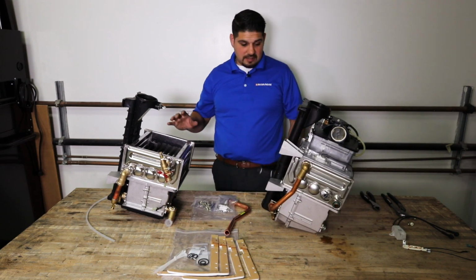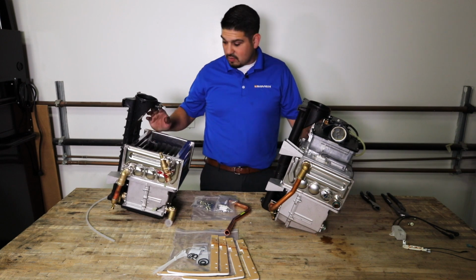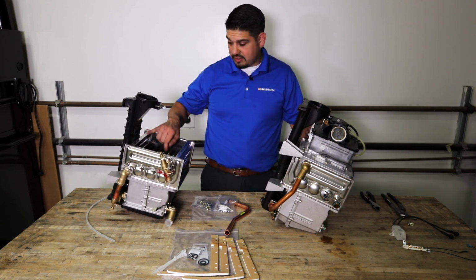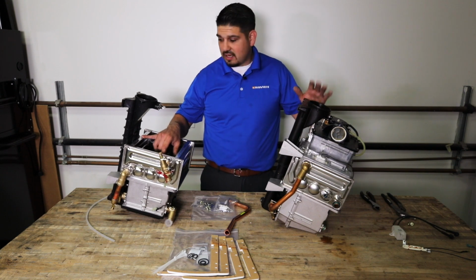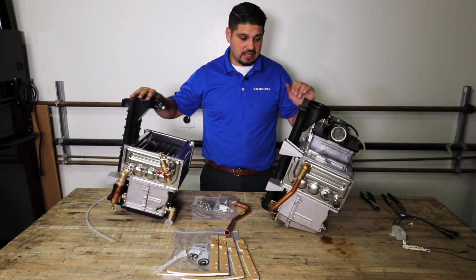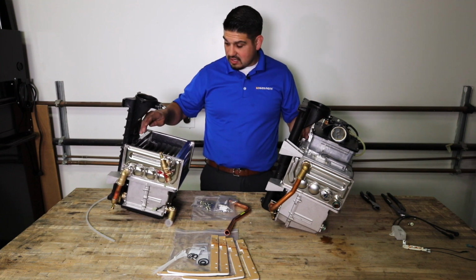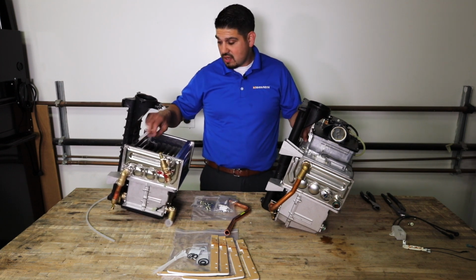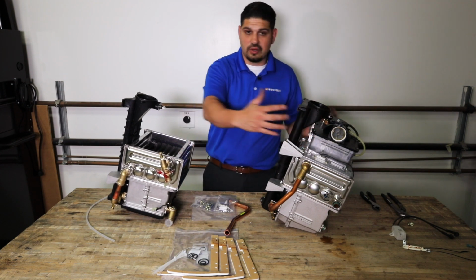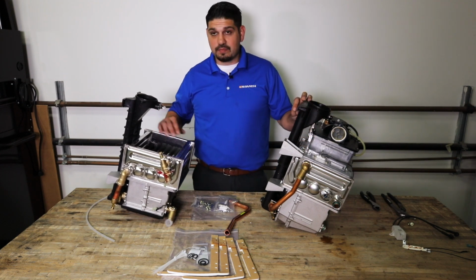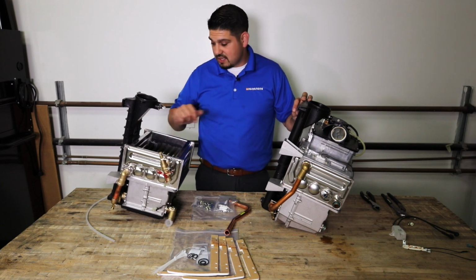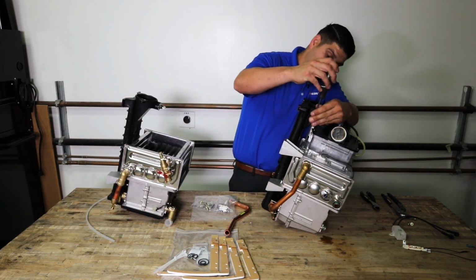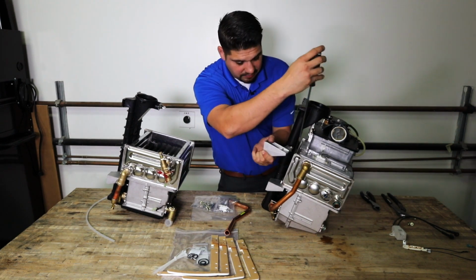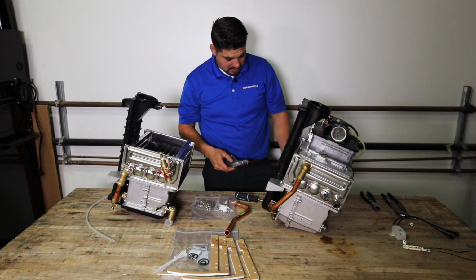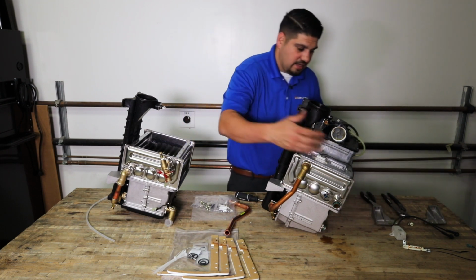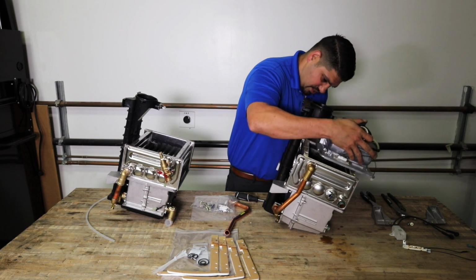With the new heat exchanger design on this one compared to this one, what they've done is there's a little hole in the middle that no longer exists. The angle of your exhaust ducts and getting a screw jammed, it was pretty hard. So what they did was they eliminated this center hole on your heat exchanger. So when you transition over your burner, you're not going to be able to put that hole in there because it doesn't exist anymore. So just go ahead and remember that. Keep these together. Keep these in the correct position. And your burner should come right off.